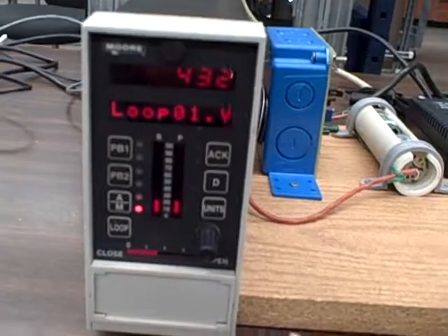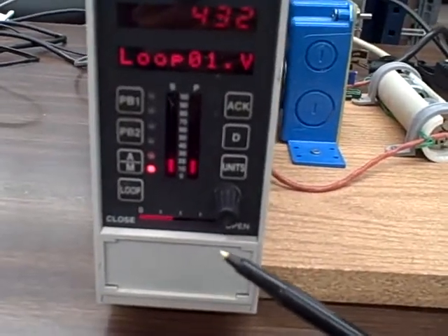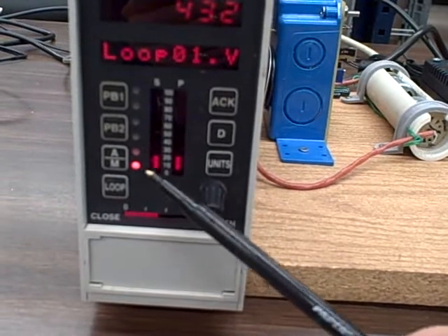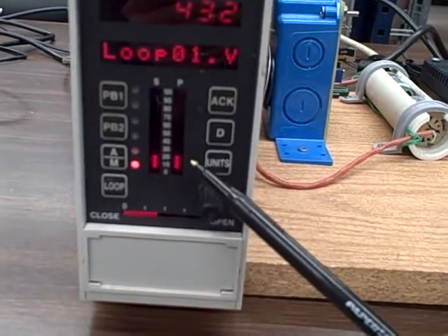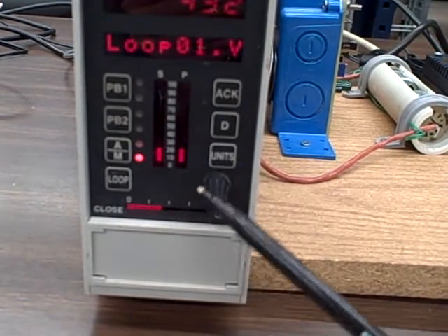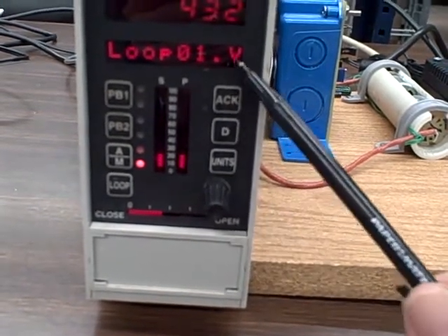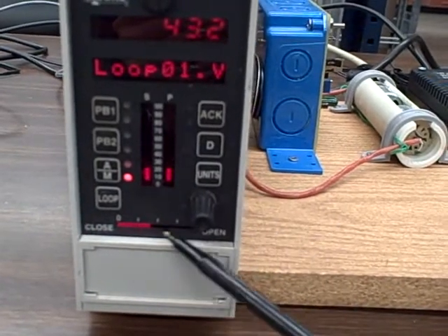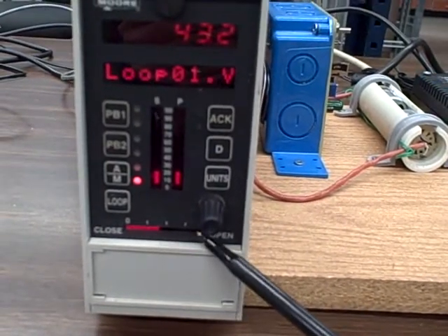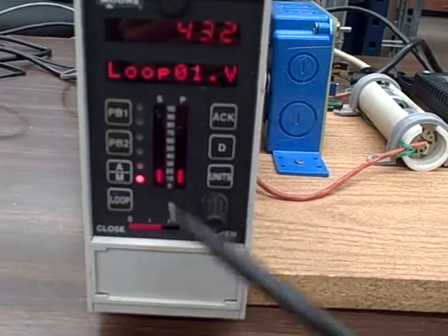Now, this particular controller, like many industrial loop controllers, has a feature called set point tracking. When it is in the manual mode, whatever the process variable reads happens to be made the set point as well. So watch what happens when I adjust the output knob here. Remember the V display for valve. The output knob, as I adjust it, and we see this bar graph go up and down for my output signal, we're going to see both the process variable and the set point rise and fall accordingly. Watch.